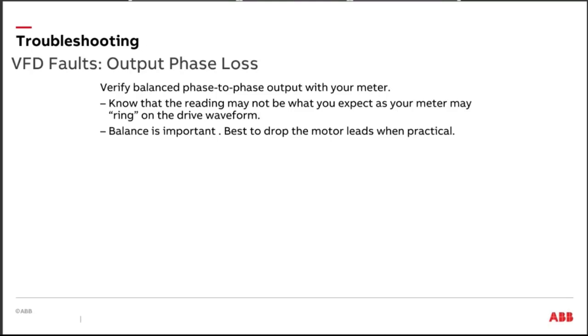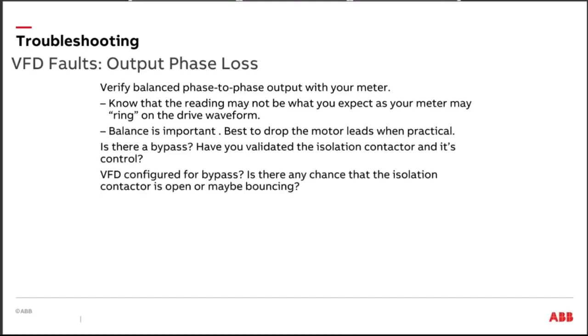Probably one of the better troubleshooting tools in the world is to look at the output voltage coming out of the drive, okay? And we want to see a nice balance between the motor leads. Drop the motor leads as close to the drive as you can, okay? If you have a bypass, and I've seen this happen several times through the years, with a bypass mechanism, you're going to have an isolation contactor and a bypass contactor. That isolation contactor prevents you from backfeeding the output of the drive when you're running in the bypass mode. So that output contactor, or the isolation contactor, is going to be open to isolate the output of the drive from the voltage from the bypass contactor.